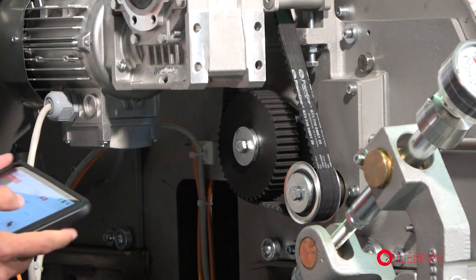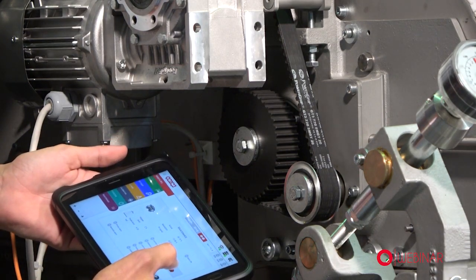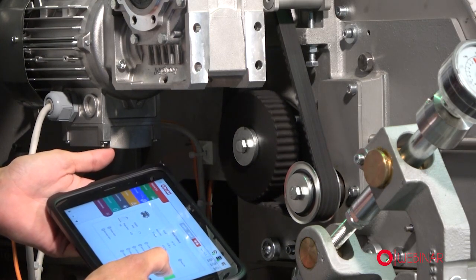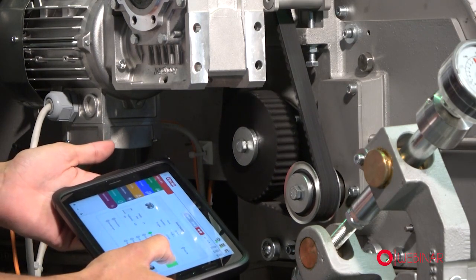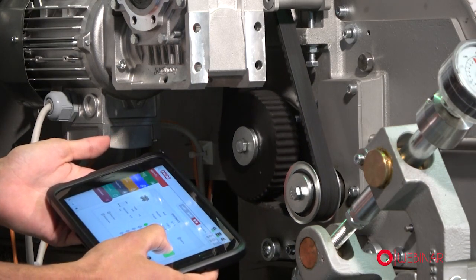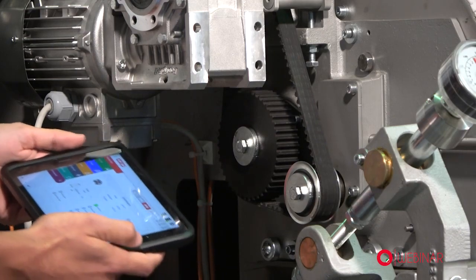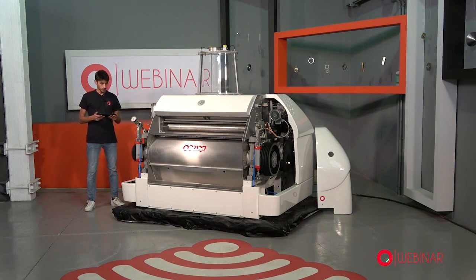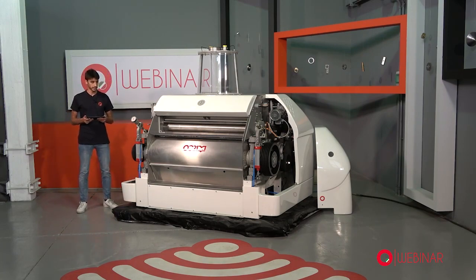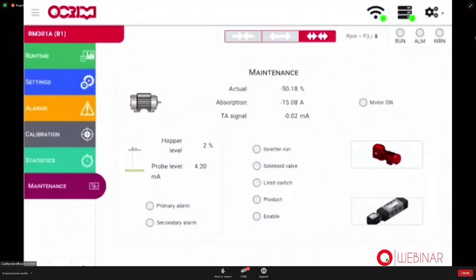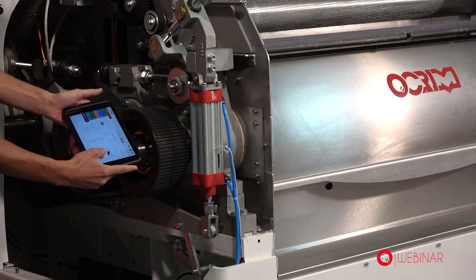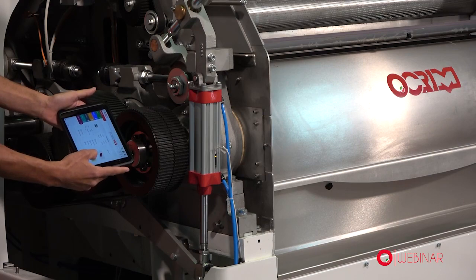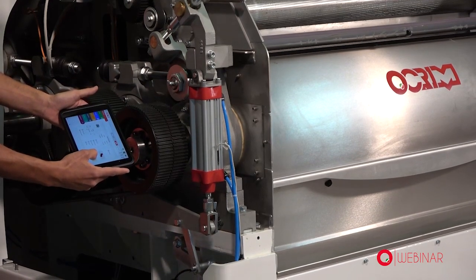On this page, we have two tests available. One for the gear motor. You just need to press the button and this will start. So the feed roller will start. You can see that the gear motor started, and thanks to the belt, the feed roller is put into rotation. Now we can also test the pneumatic cylinder, which manages the movement of the milling cylinders. You can see this icon of a valve. In this case, you can activate the electrical valve that will control the pneumatic cylinders. And this is the movement from the pneumatic cylinder.